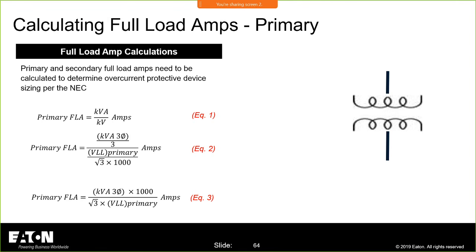I'm including them here as well, how to get the full load amps. You know, full load amp calculation. I did a class one time, I had 80-some students in the class, and we were talking about transformer protection. And I said, okay, the first step in anything, you're going to have to calculate the full load amps.